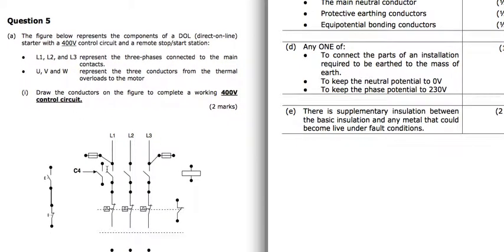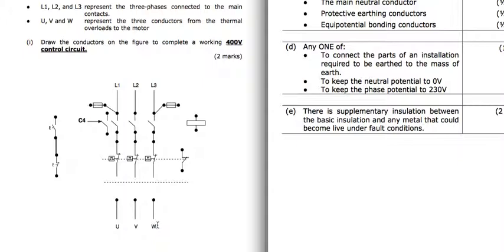Question 5, we've got the components of a DOL. We've got L1, L2 and L3, and we've got our motor there, UVW. We've got our overload there and our overload contact there, some fuses and a contactor, and that contactor is going to control these 4 contacts. So these 3 are going to put our supply through to our motor, and this one is going to be our holding contact, and that holding contact is going to make sure that when we release the start switch, the motor will still go. It holds the supply to the motor.